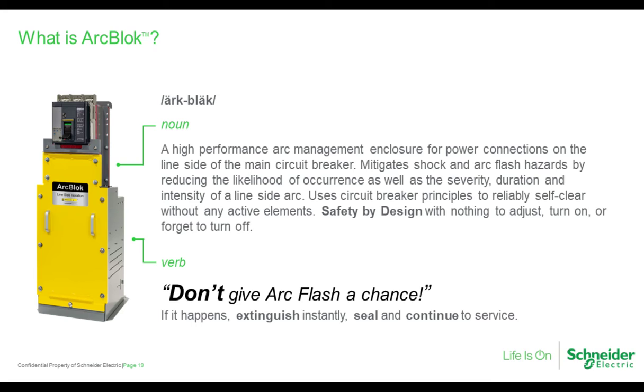However, arc flash incidents still can happen. We all accept that, right? For example, humidity and environmental conditions may be one of the root causes. So if it happens, this innovative technology also reduces the arc flash incident energy levels significantly. It's around 1.2 calories per centimeter square. In other words, it's a system to minimize the human risk factor and reduce the arc flash incident energy level.